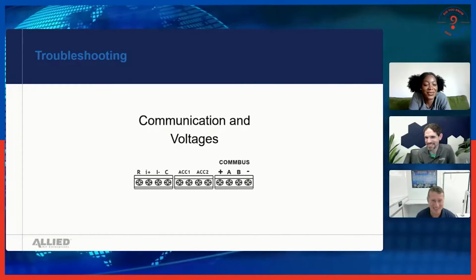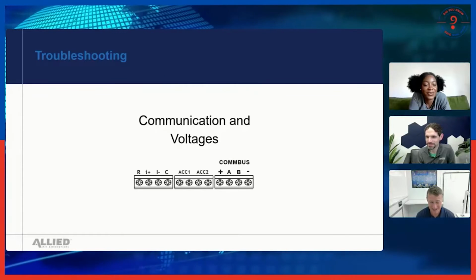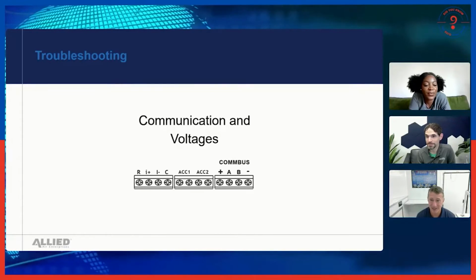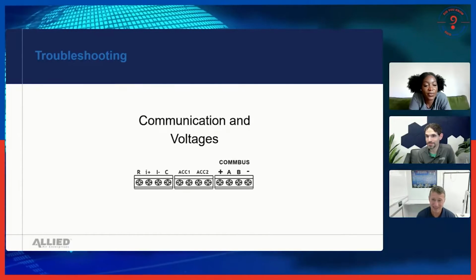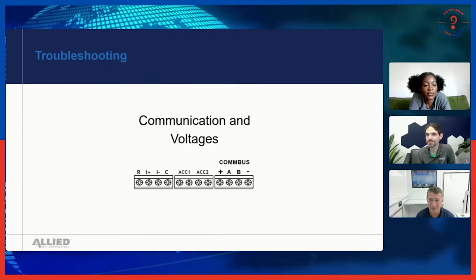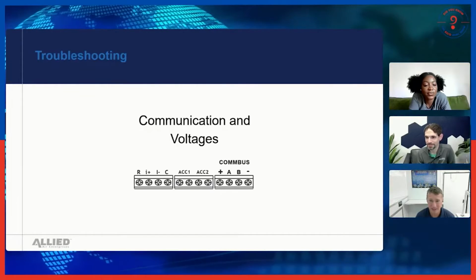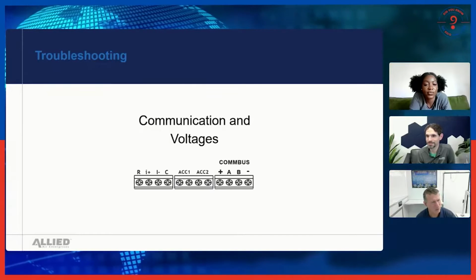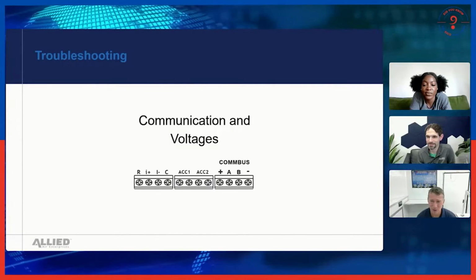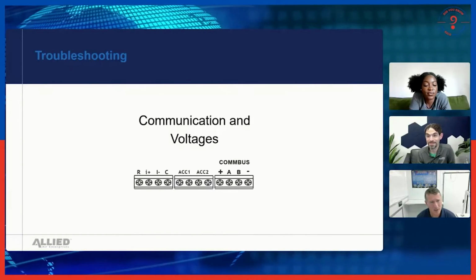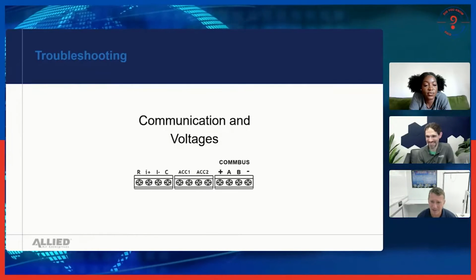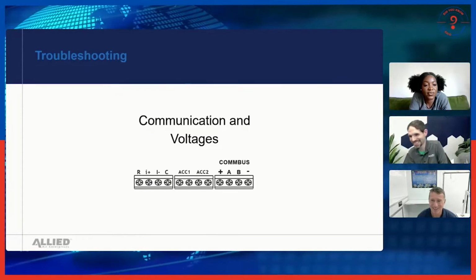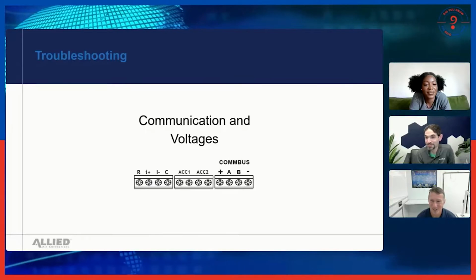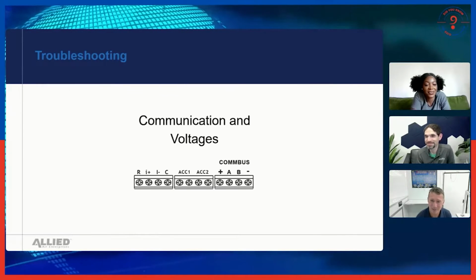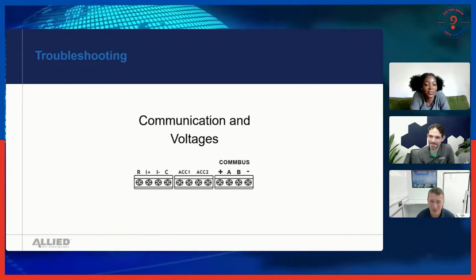I pull out the installation manual for this equipment, and it actually says that this communicating piece of equipment should be at least 60 inches away from any type of television, radio, or broadcasting equipment. I asked him, so how often do you use your ham radio? He said, well, I'm in a club and every Sunday night we have our meetings and we talk. And I said, well, every Sunday night you're throwing an error code on your system that's coming up on your communicating thermostat. And he's like, I don't understand how we do that.